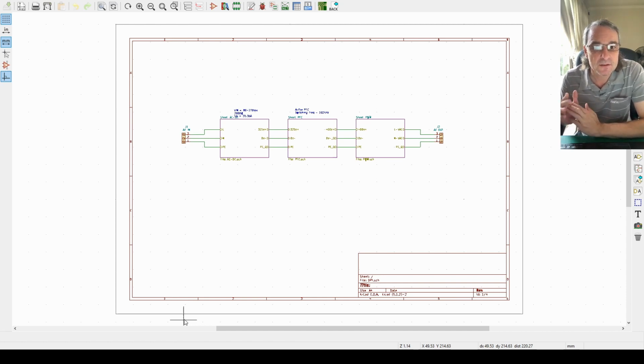And the more I dug into this thing, the more I realized that it is not a true full inline dip-proof inverter. In other words, what this thing does is it monitors the control voltage, and if the control voltage dips below a certain percentage, then this thing will switch in. So whatever noise is in the power is being passed straight through to the contactors until this thing kicks in, which to me was a bit of... it wasn't really my way of thinking.